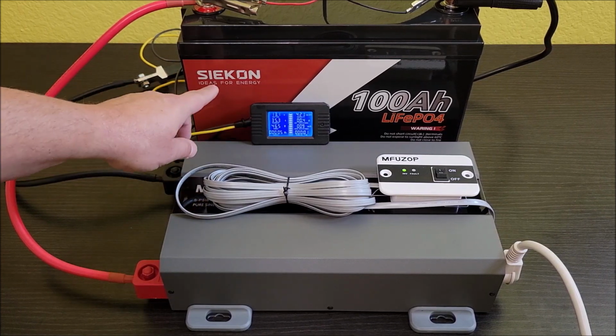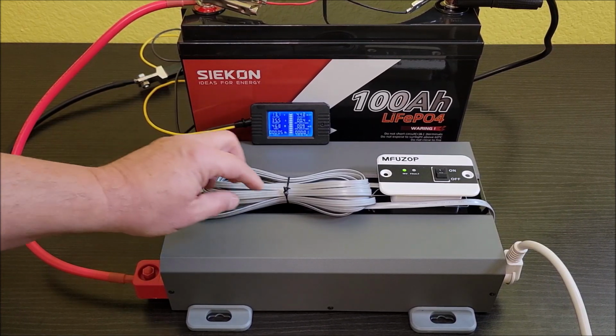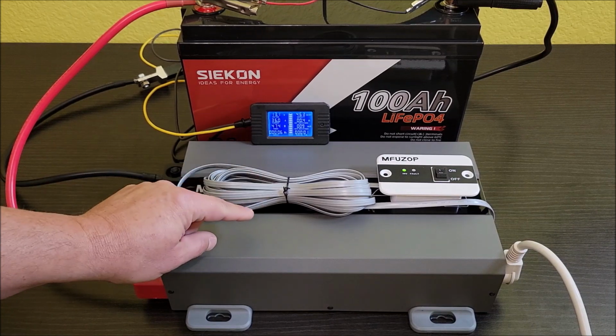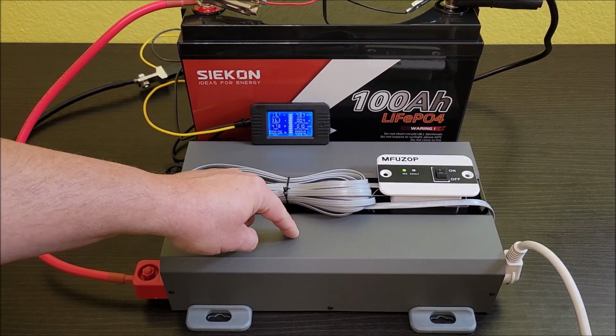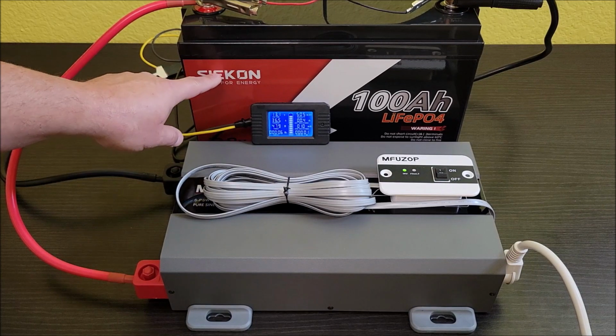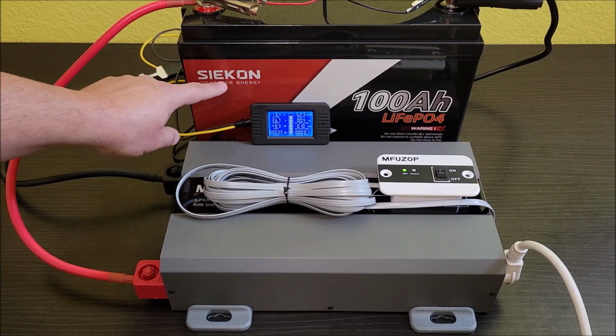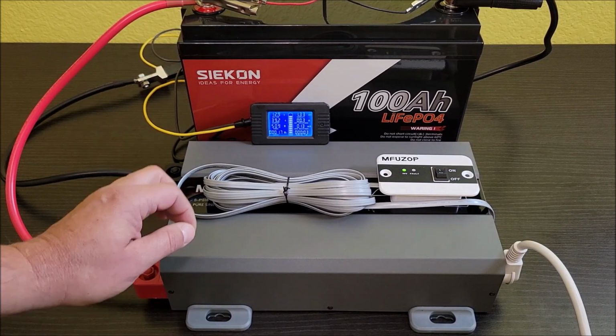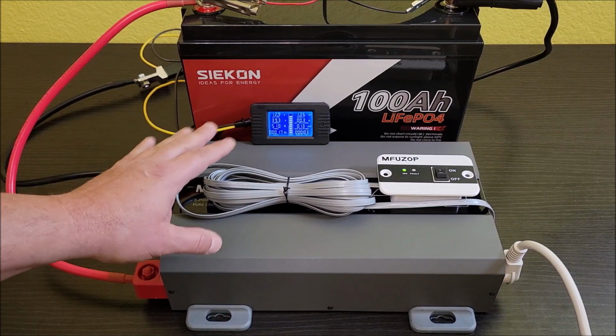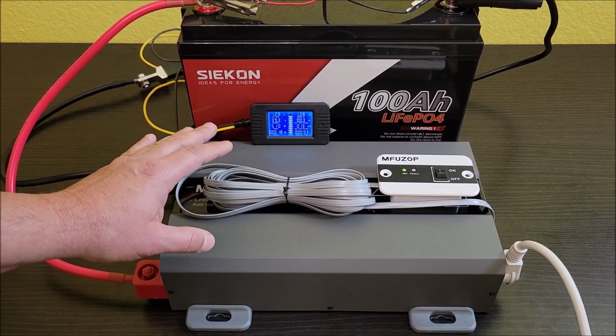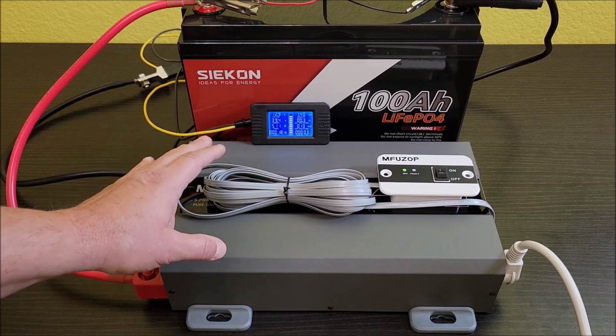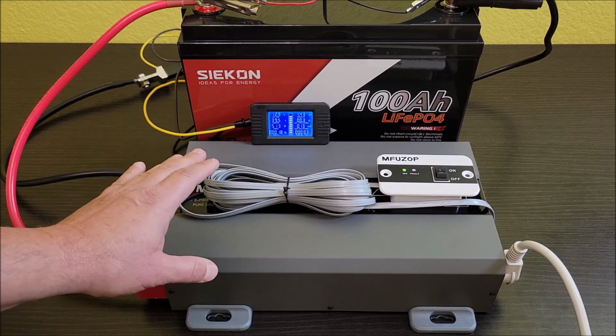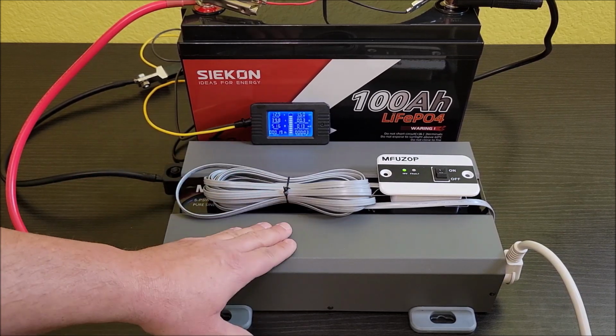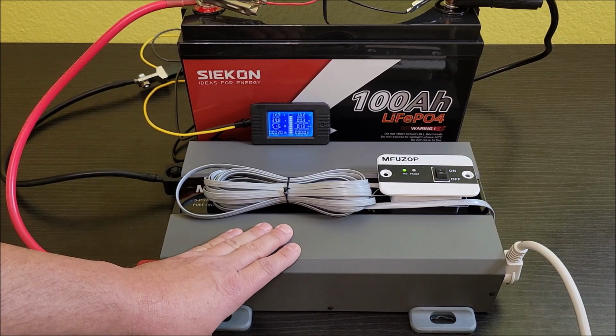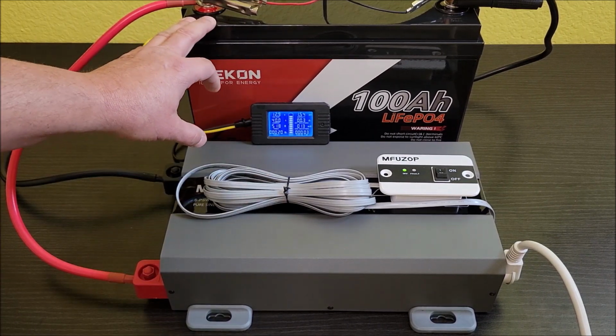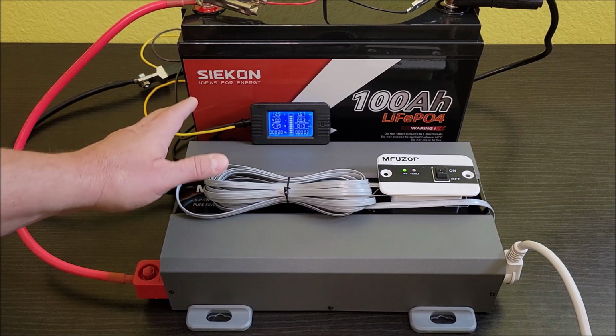It did peak out. The thing to note here is that when the air conditioner did kick on, it peaked out this inverter, which then sends the load to this battery, and the battery was able to handle that. When I can catch it on the battery monitor, I have seen this compressor kick all the way up to 2.5 kilowatts of power, which is beyond the specs on this inverter and well beyond the specs on this battery, but it still was able to handle it with no problem.